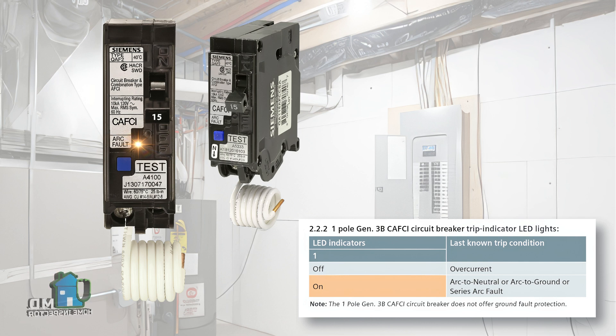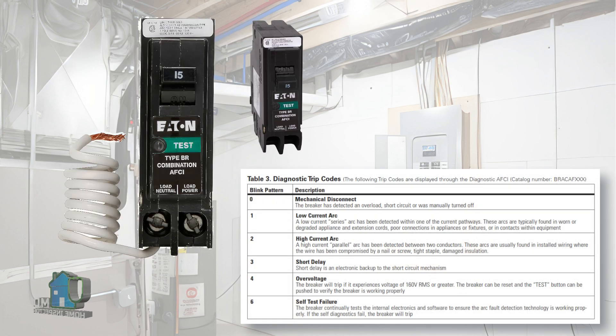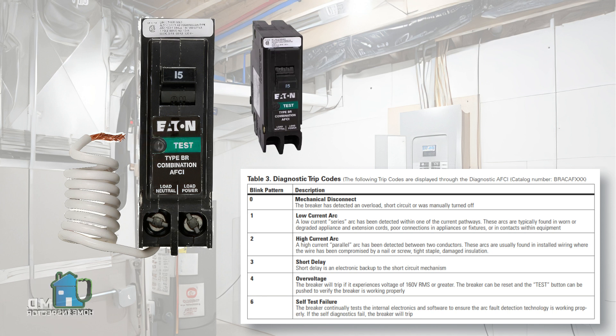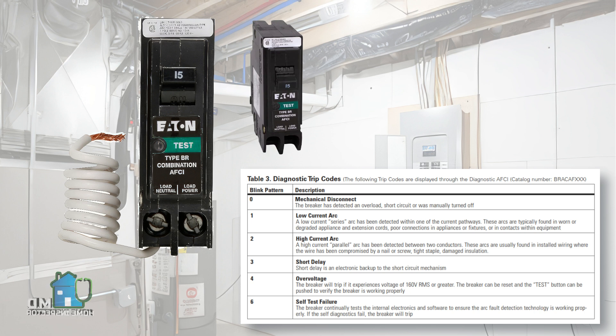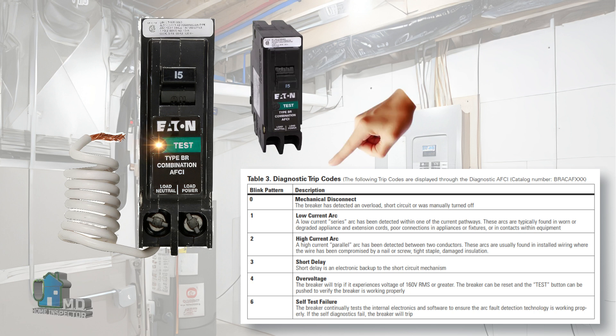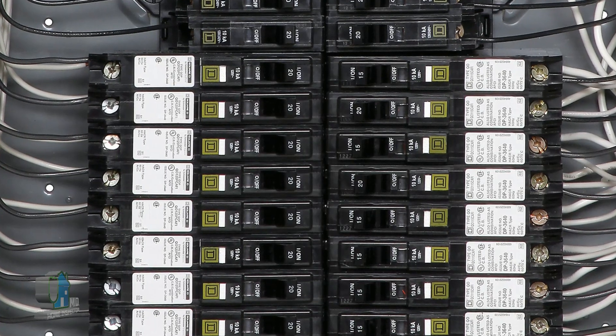What about Eaton circuit breakers? The most common Eaton breakers in Canada are the BR type. They have their own version of diagnostic trip codes and also use an LED, but they use a blink pattern instead. Eaton does it a little differently — the number of blinks indicates the problem. For example, if you see two blinks repeated, it means the problem is a parallel arc.